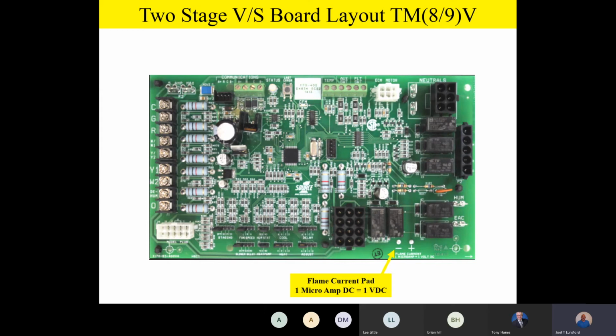And again, just plant this in your brain. If you have low flame current, the #1 cause is going to be poor grounding. And then the #2 cause right behind that is a dirty flame sensor. So keep those in the back of your brain if you're having some flame sensing or low flame current conditions. There's our 12-pin harness, 24 volt inputs and outputs. Again, team, you're going to find that your gas valve and your pressure switches and your safety circuits and your FP, your flame proving circuits, will all be plugged into that 12-pin harness.